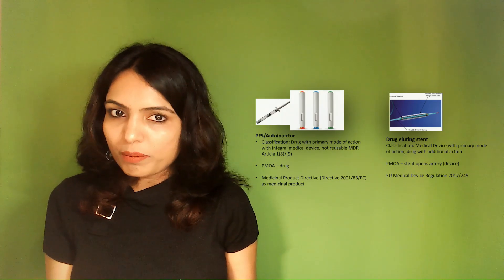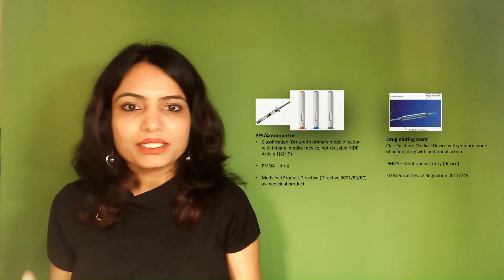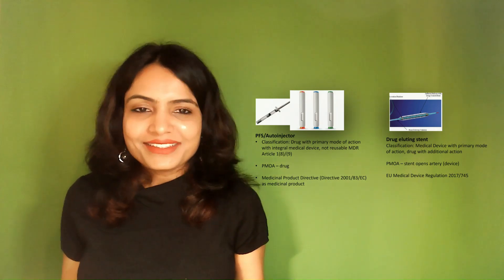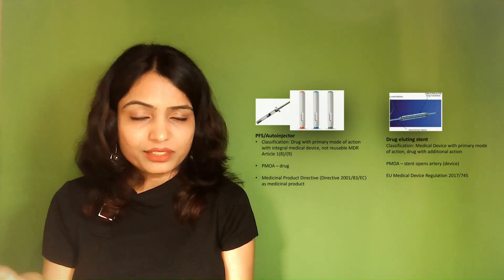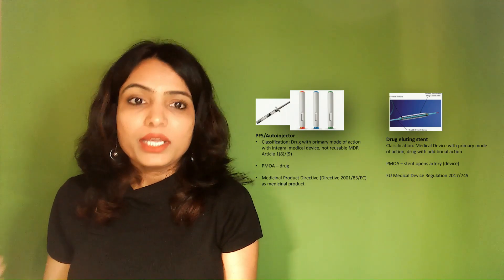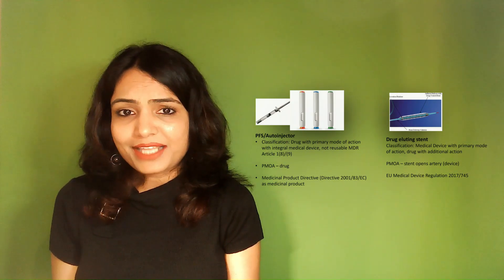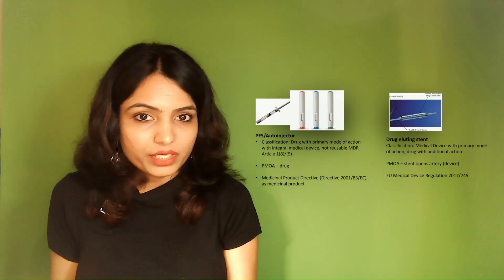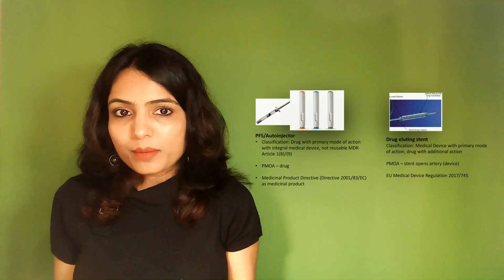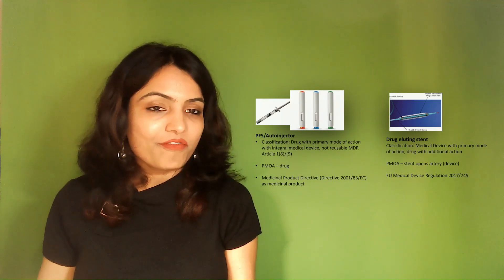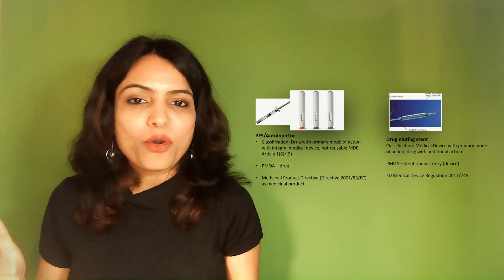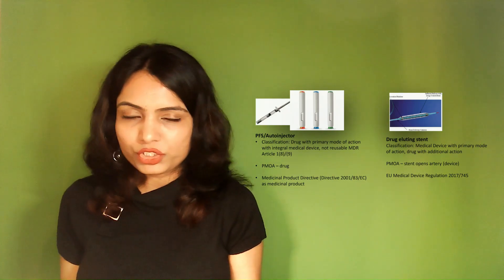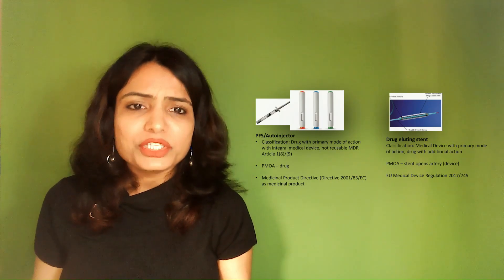In addition, the device part of such a combination product also has to fulfill certain requirements under medical device regulation. For a product like a pre-filled syringe or auto-injector, the driving regulation is the drug regulation because the primary mode of action is due to the drug. By contrast, for a drug-eluting stent, the stent is used to open the artery while the drug's function is secondary — to reduce inflammation — therefore the entire product is regulated by medical device regulation, because the primary mode of action is due to the device.